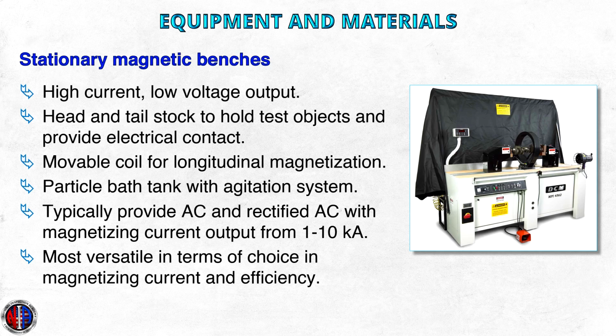Of all the equipment available for magnetic particle testing, a stationary bench system is the most versatile in terms of choice in magnetizing current and efficiency of operations. Stationary magnetic particle bench systems are designed to be ergonomic with conveniently positioned control functions. The instrumentation includes liquid crystal displays for digital readouts, or meters in older units, of amperes and smart knobs for fine-tuning of settings. Stationary systems are designed for rugged durability and require minimal practice to operate effectively. Many also have a step-down transformer needed for demagnetization. Bench systems require an array of process controls and maintenance to validate equipment, materials, and processes.